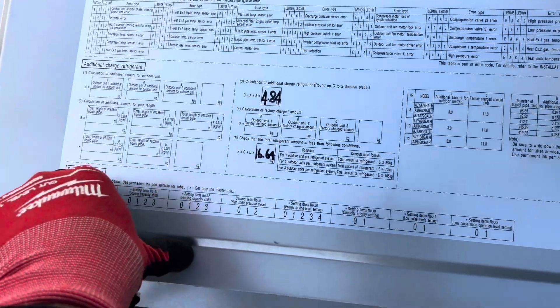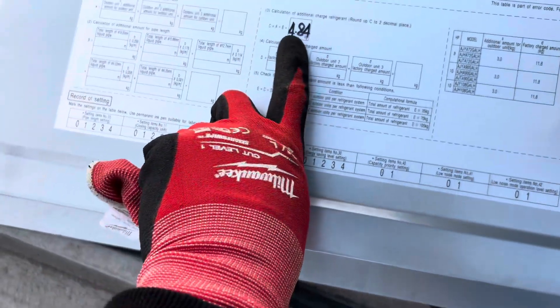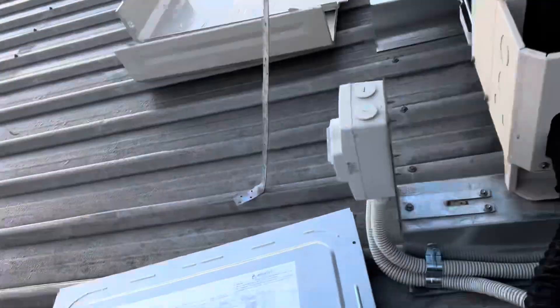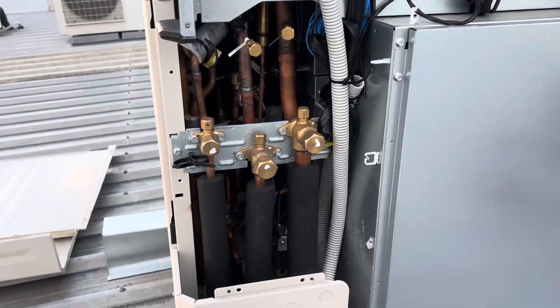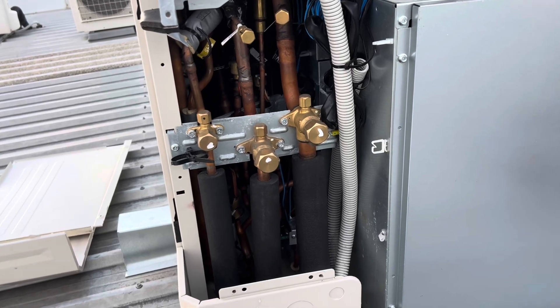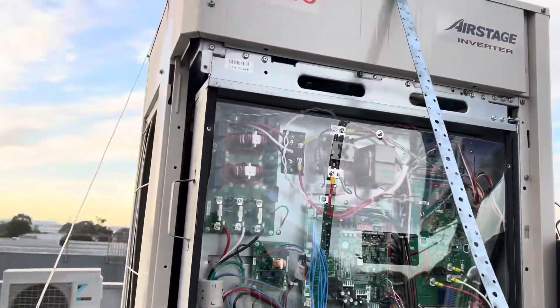I hope we're going to be able to pump this thing down. You can see the additional is only 4.8, so I think it's 16.64 in total. We'll pump it out as much as we can and then recover the rest of the gas if we need to. Looks alright so far, doesn't look too bad.